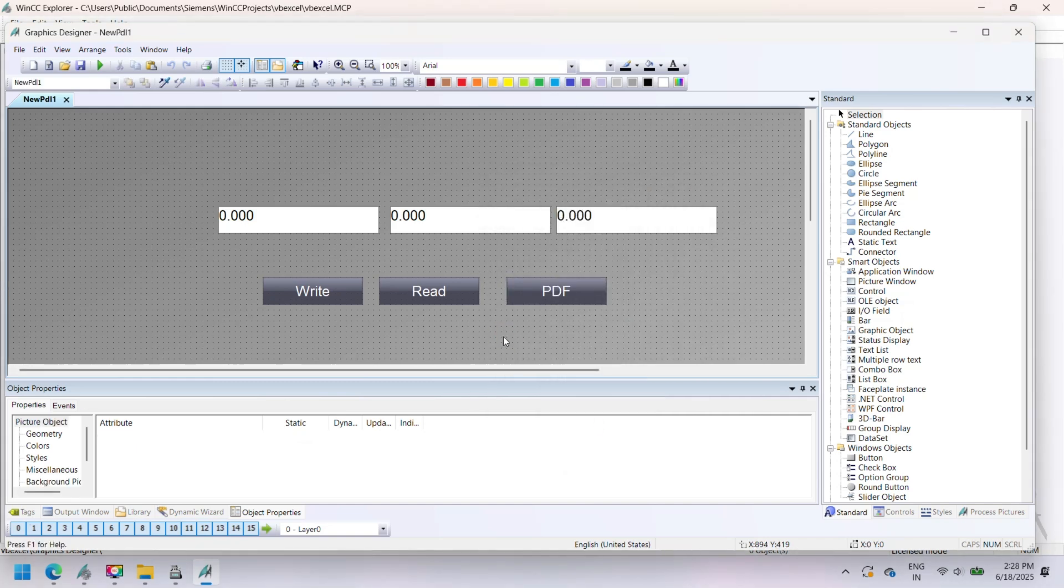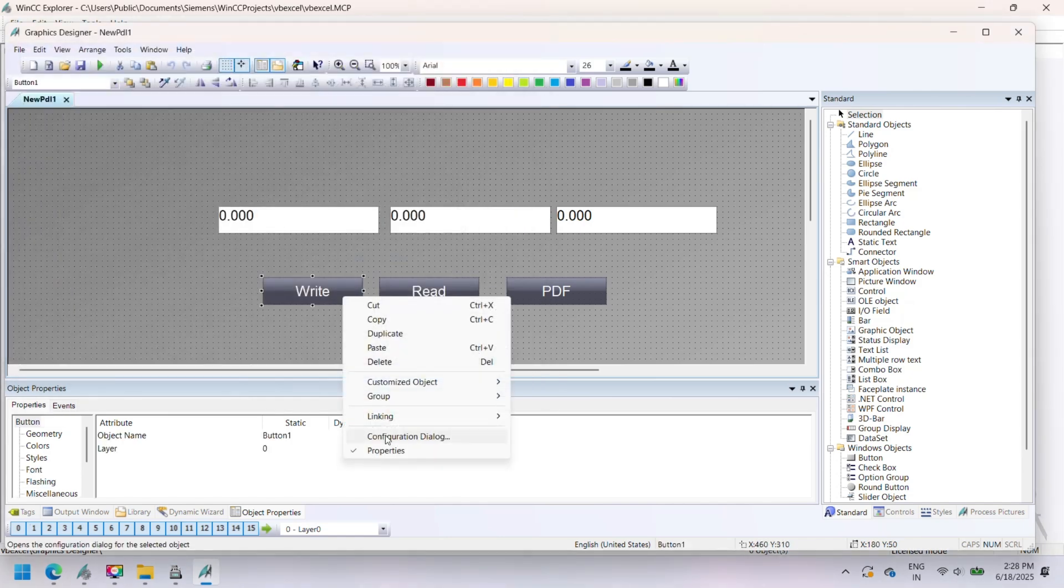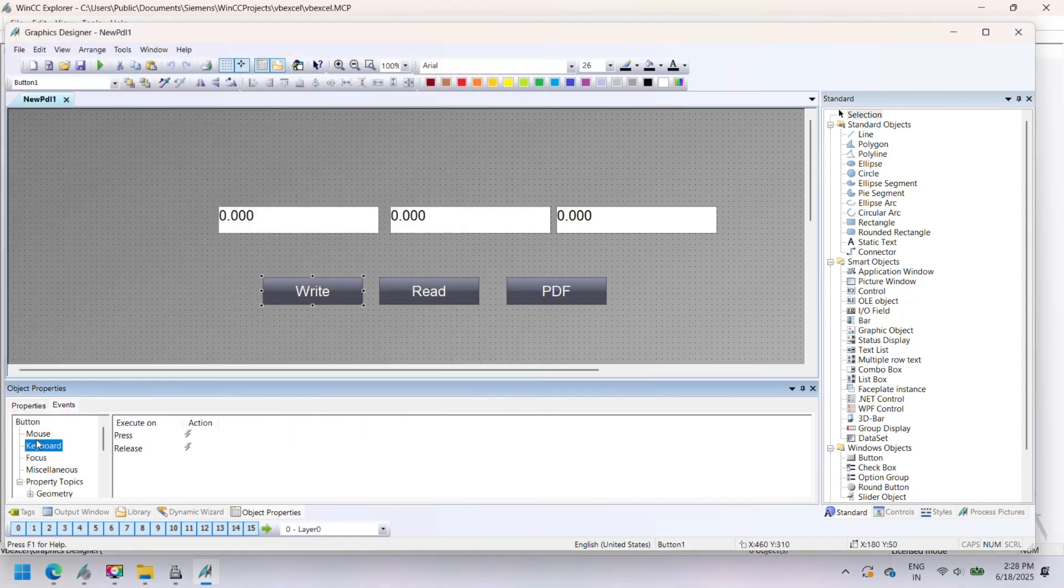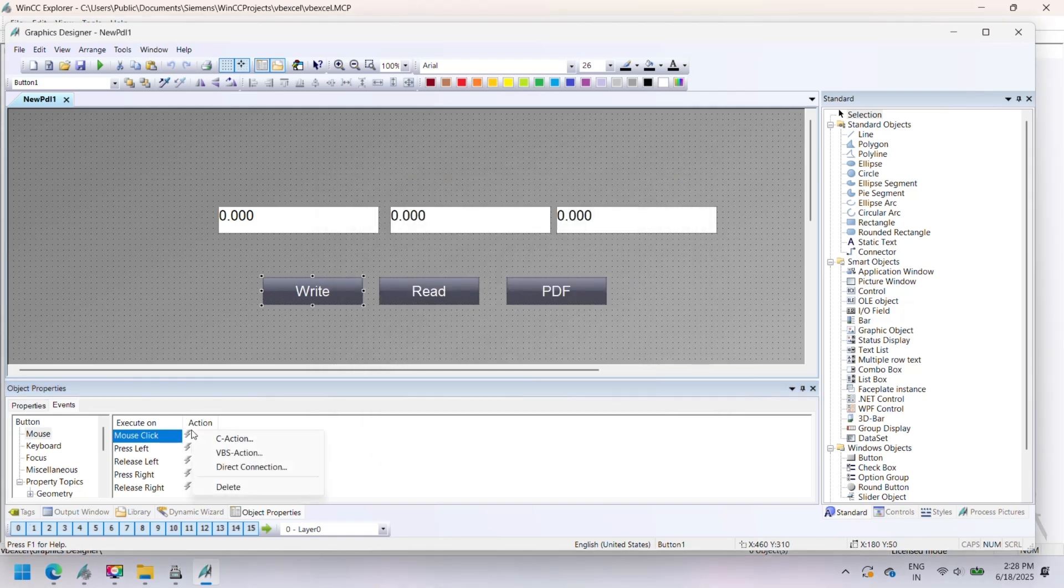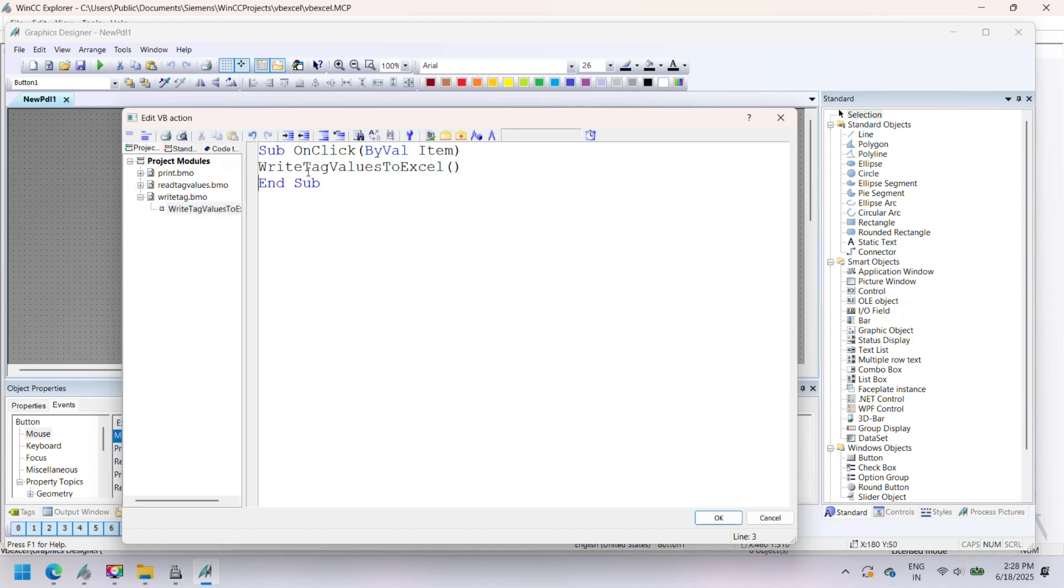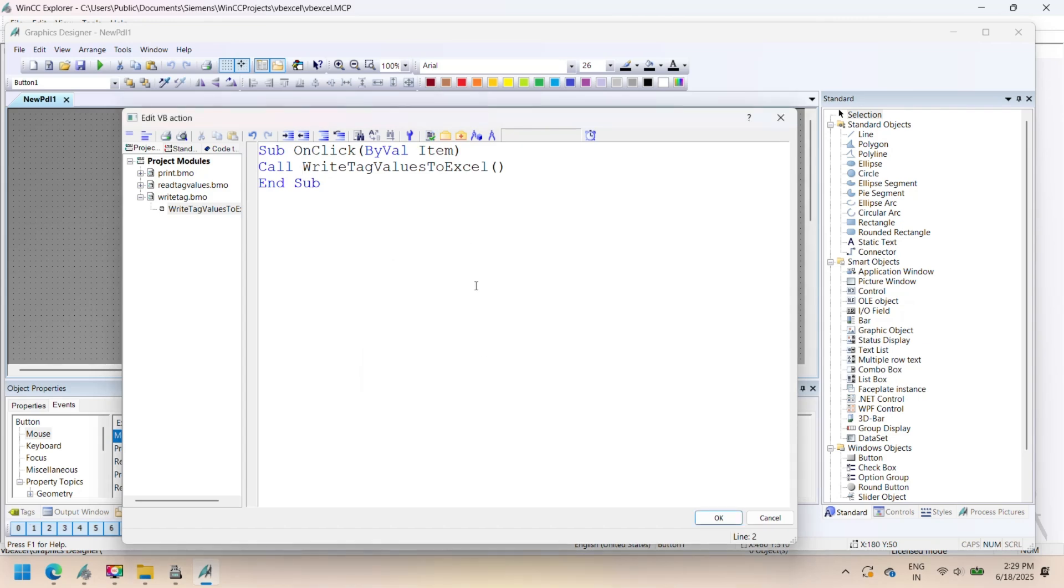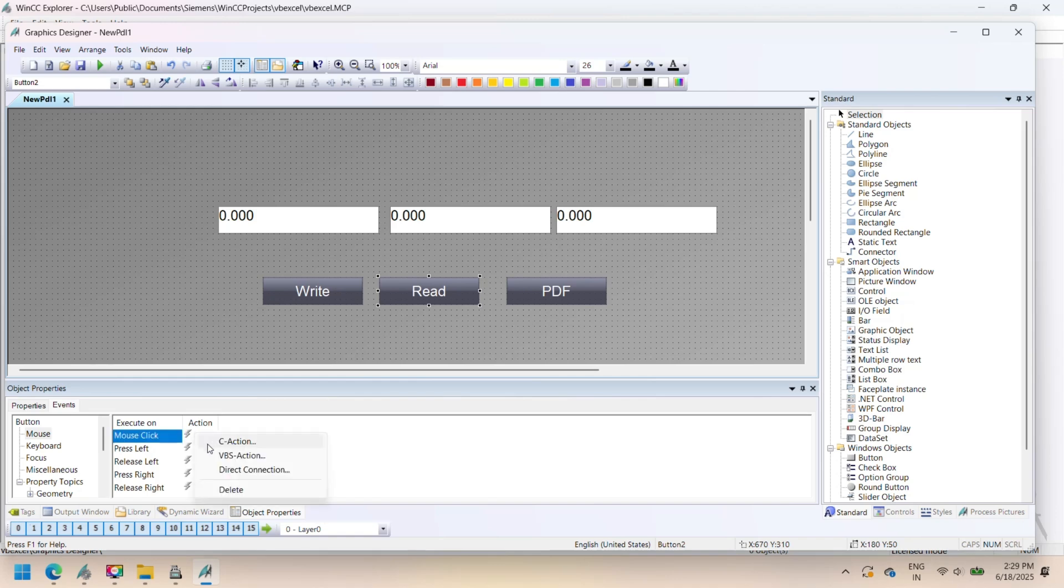Open the Graphics Designer in Siemens WinCC and design your SCADA screen for Excel data interaction. Add three input-output field elements and assign the tags which were previously created in Tag Management. These fields will be used to display live data from the SCADA system and allow operators to input values if needed.